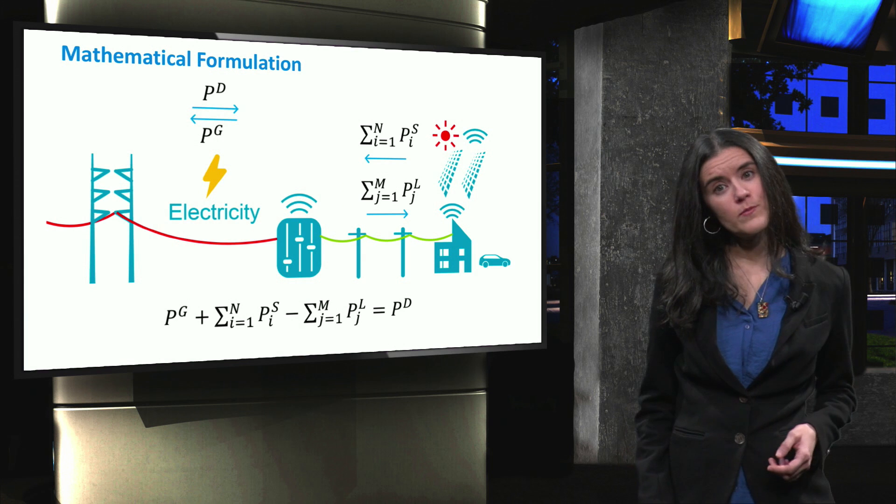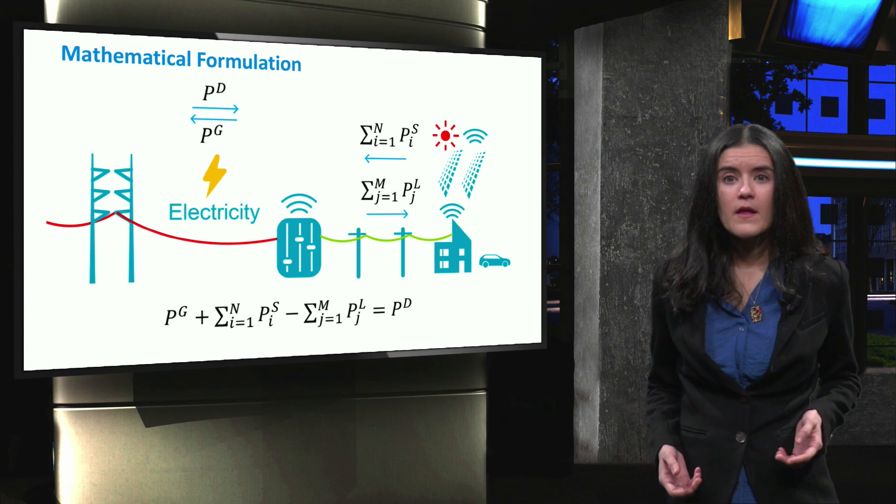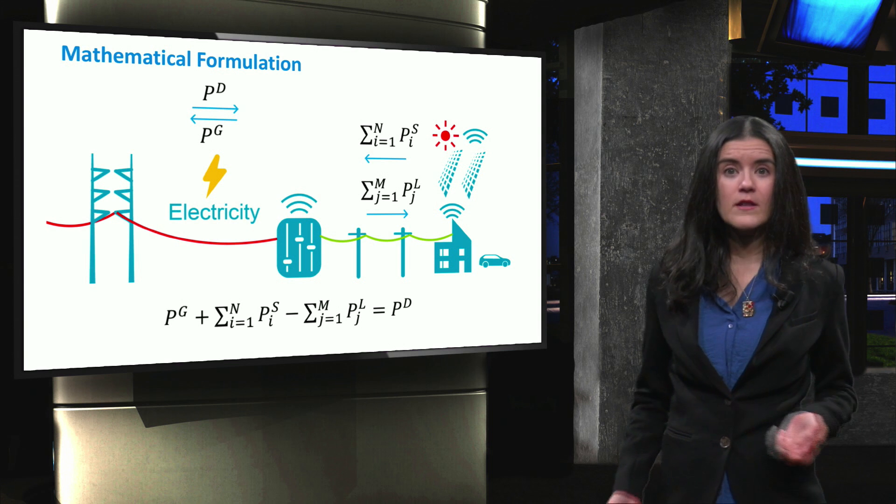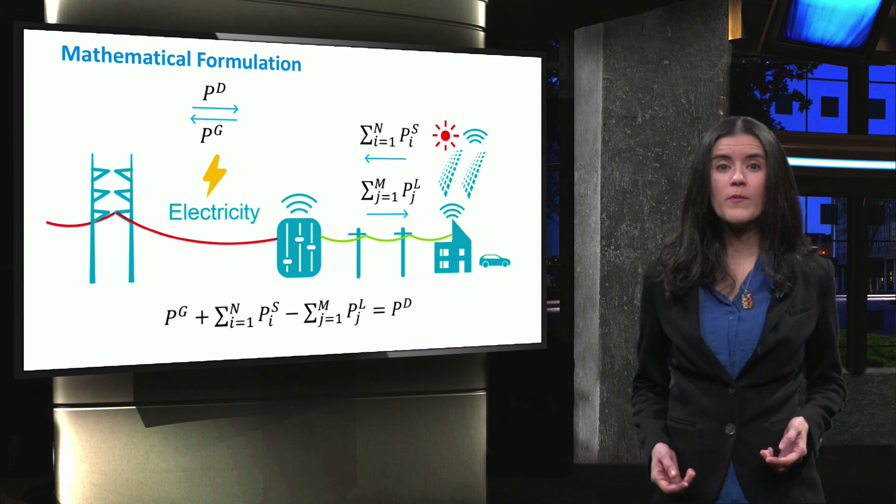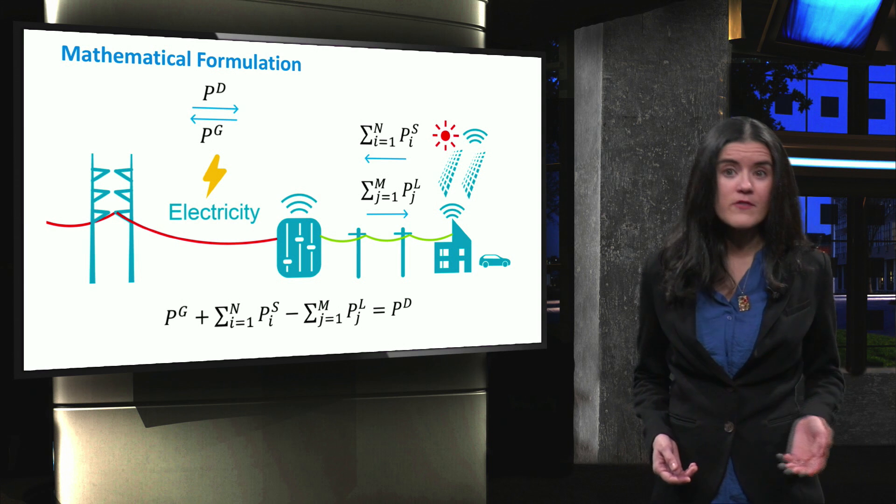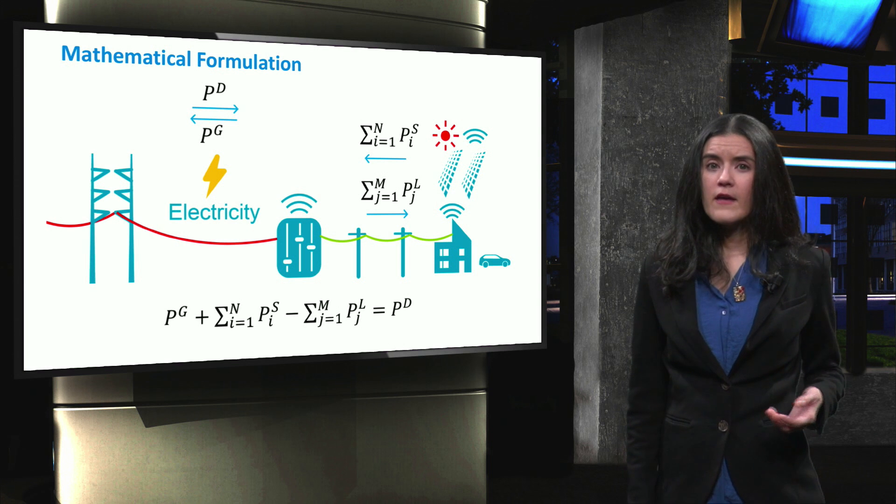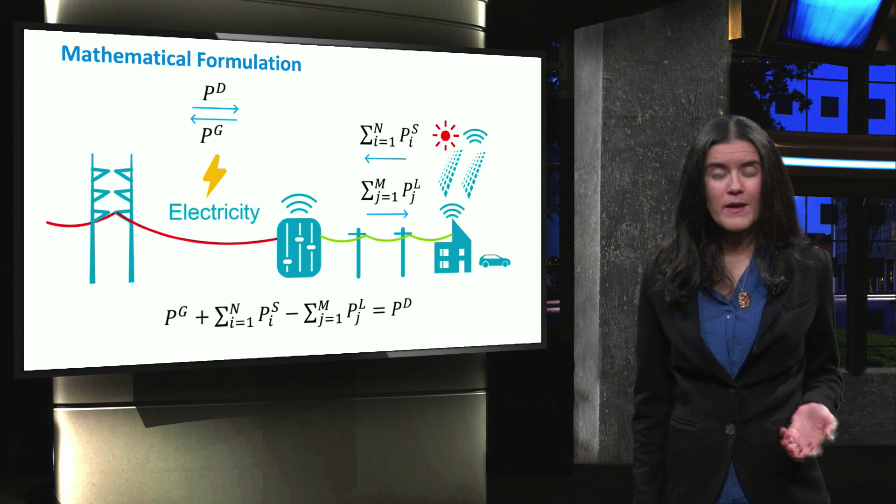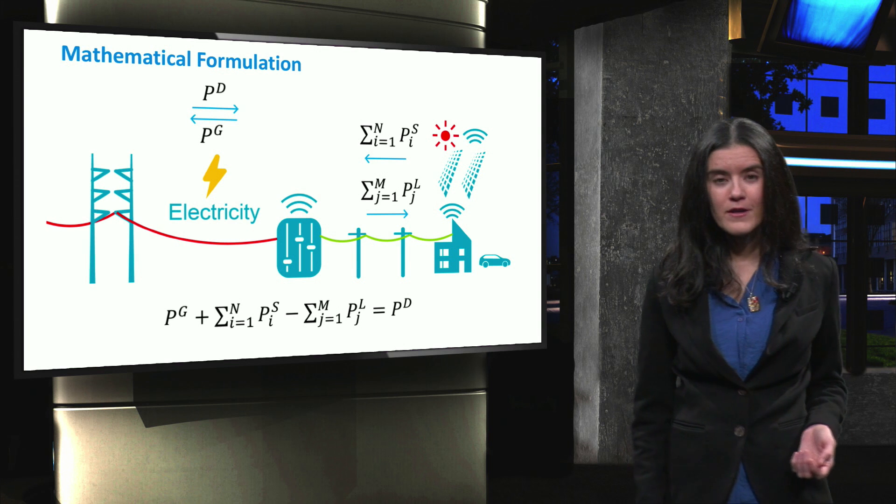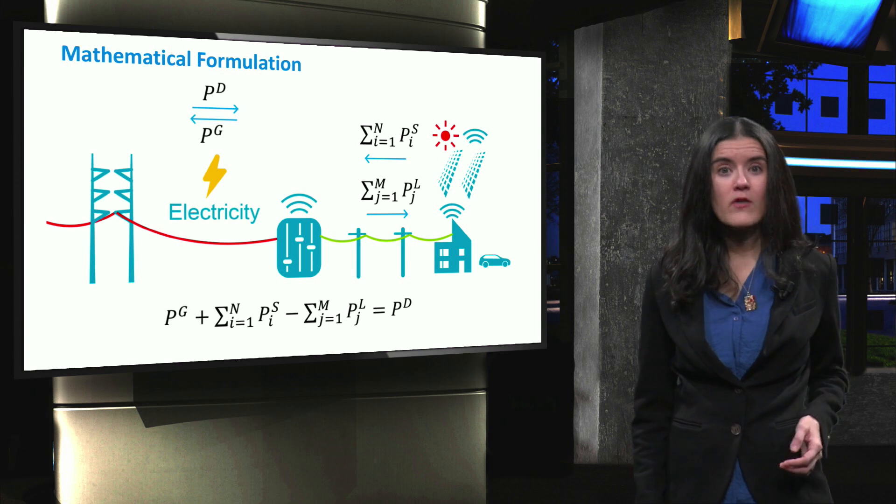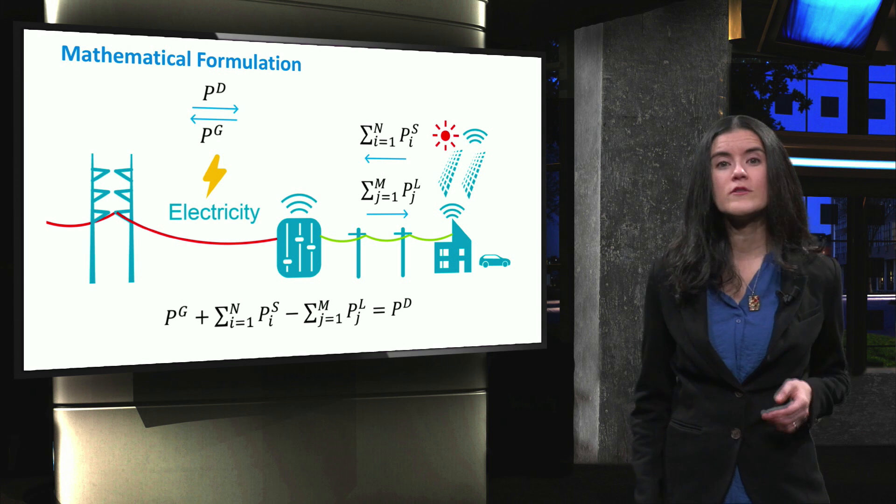In every optimization problem, there are constraints to which the objective function is subject to. In microgrids, examples of constraints are the technical limits of distributed generation sources like the minimum and maximum limits of operation, active and reactive power curves, and the start-up times. If power exchange with the main grid wants to be avoided, another important constraint can be the active power balance of the microgrid, meaning that the total power generation within the microgrid at the point of common coupling is equal to the power consumption.